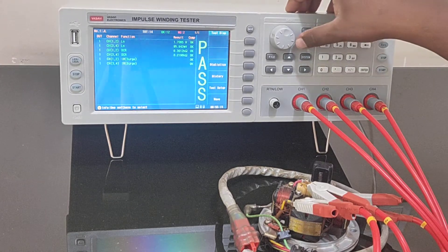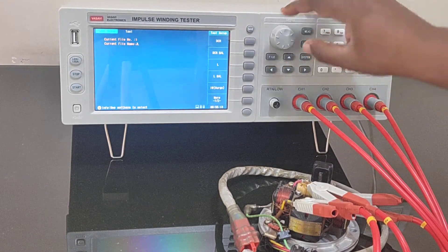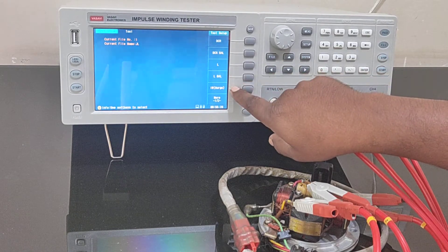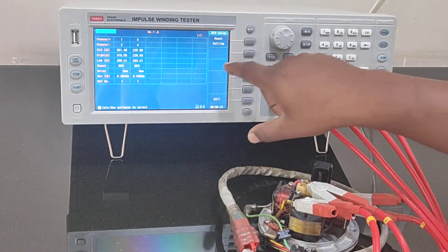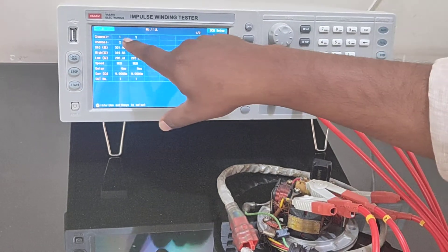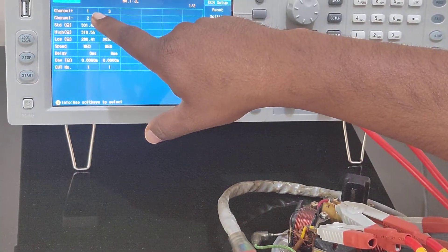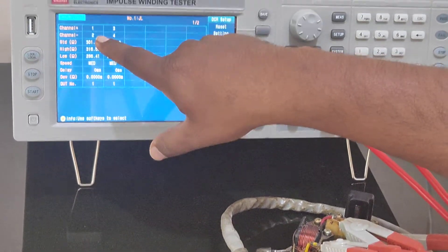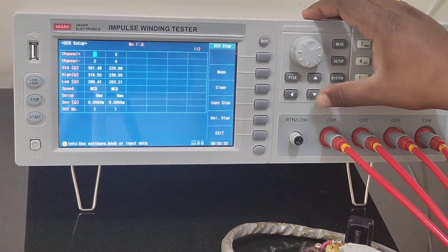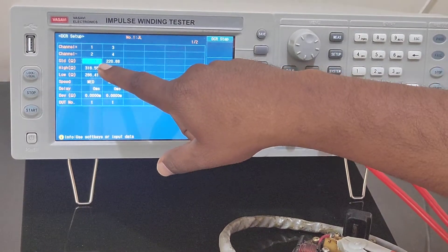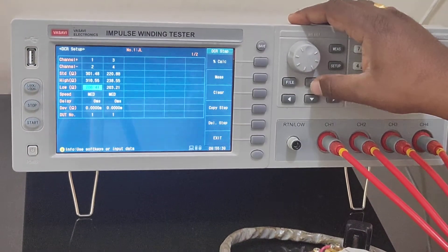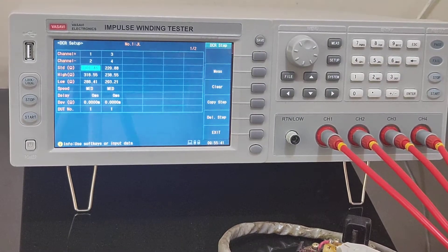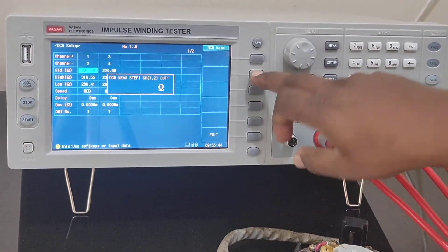Now I'll show you how to program for a coil. You press setup. Over here you have functions - what you want to select. DCR - this is channel 1. Start I have given as channel 1 and end as channel 2. Over here is the expected value, this is lower limit, upper limit.